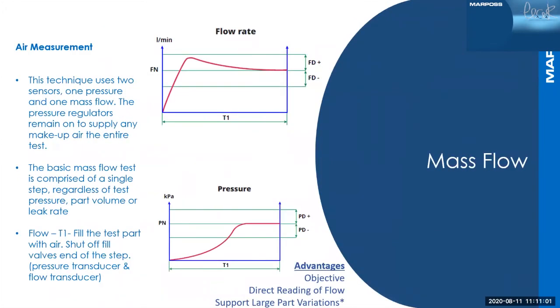So the first way we look at it with air measurement, this is just on a flow test. It is normally configured with a single step. You'll notice two graphs, one for the test pressure and the other for the mass flow sensor. Some of the objectives when we're looking at using mass flow: you get a direct reading of that flow, and it does support large part variations without the requirement for a master part.